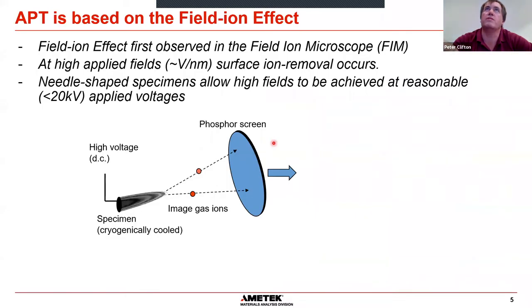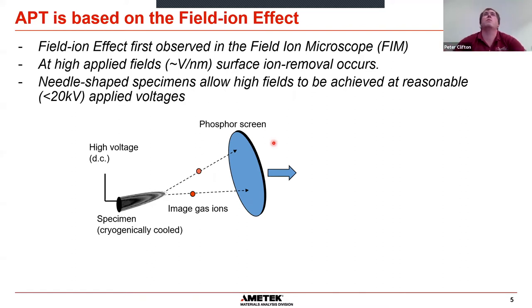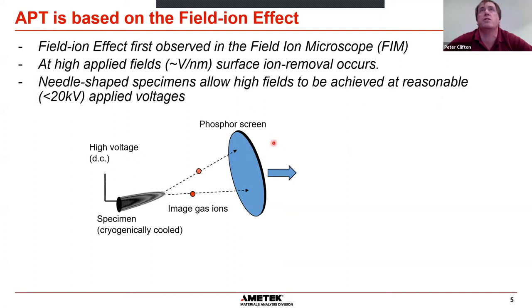Moving atoms one at a time sounds like magic, but essentially we use a high field to remove the atom. If you have a flat surface you need a really very high field — tens of volts per nanometer — to stimulate surface ion removal. Fortunately, if your surface is curved, this gives field enhancement and you need less voltage. If you can make a specimen which is a sharp needle with a tip radius of around 100 nanometers, for a modest specimen voltage we can achieve the fields we need.